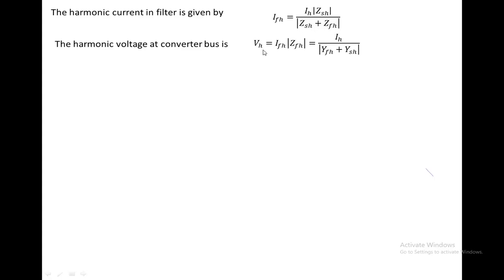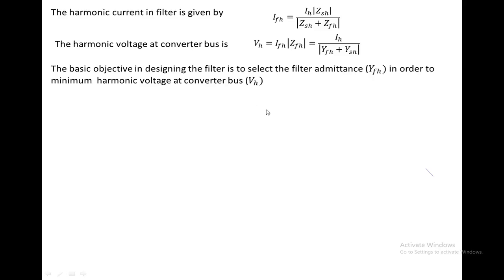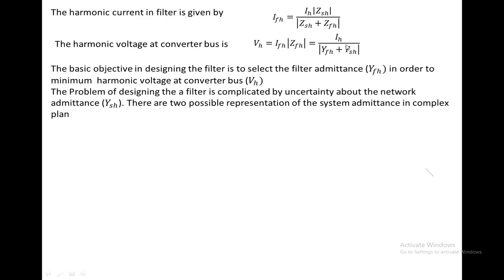From that circuit, the harmonic current in the filter is given by IFH = IH · ZSH / (ZSH + ZFH). VH is the voltage at the converter bus, which can be written as IH divided by (YFH + YS), where YFH is the admittance of the filter due to harmonics and YS is the admittance of the source due to harmonics. The main objective of filter design is that the harmonic voltage should be minimized. However, the source admittance is very difficult to measure due to uncertainty about the network.